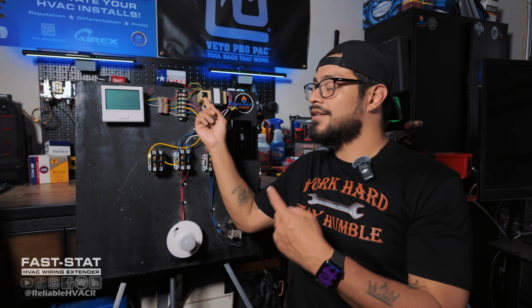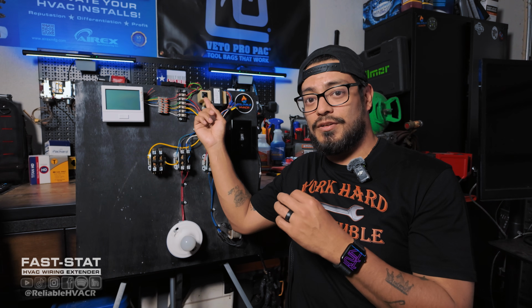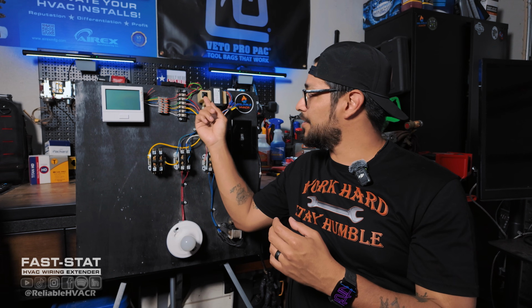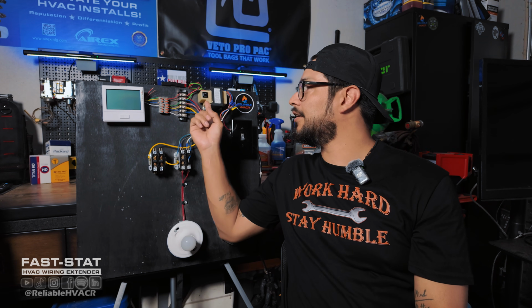There are also some of these that have a resettable fuse. This one right here, you see that more on commercial. If you're doing residential, you're going to see an actual fuse in line, either on the control board or somewhere in line on that 24 volts. And if your system is not coming on and you don't have that 24 volts, you need to check either your transformer or that fuse down the line. If this is tripped right here, or if that fuse is popped, then you immediately know you have a short.